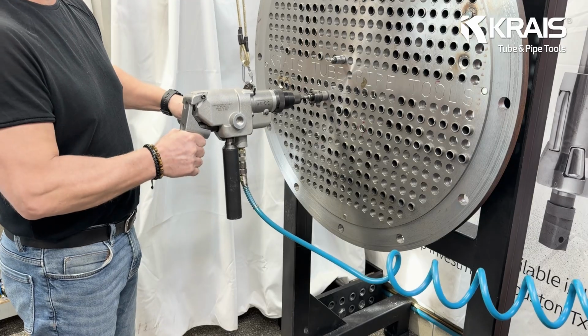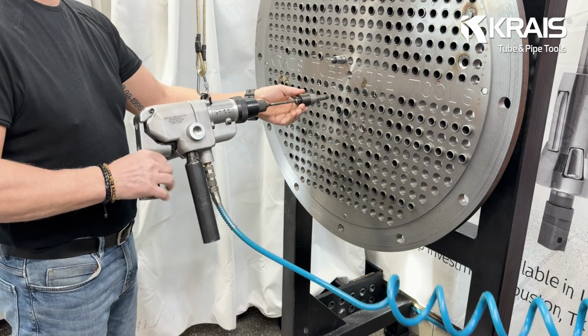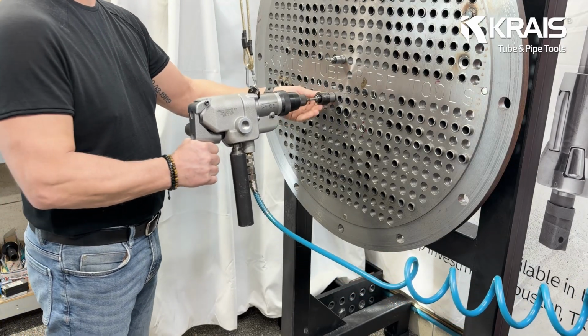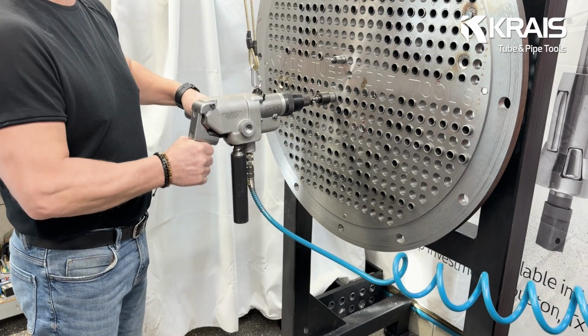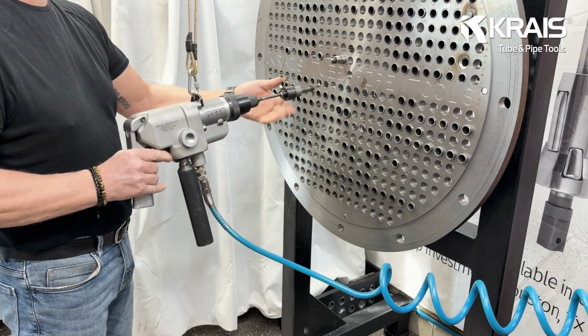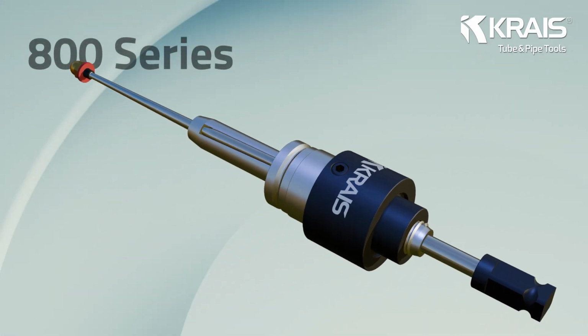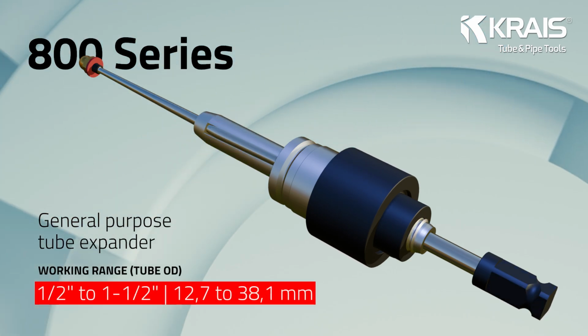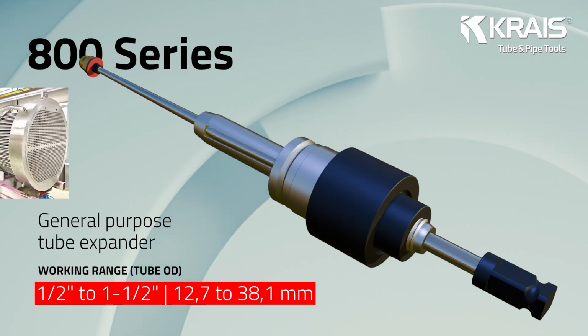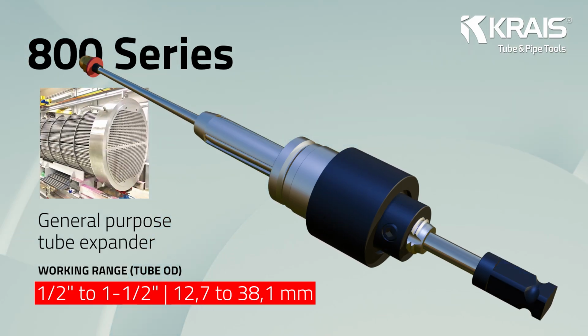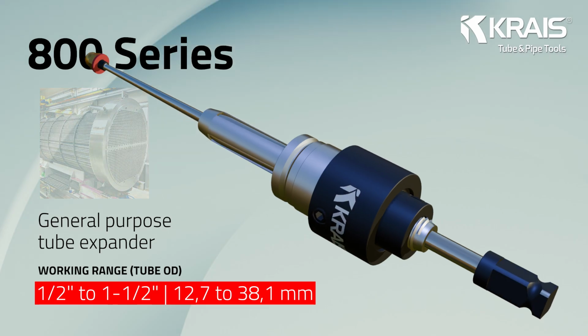In this segment, you will most often see tube ODs from 1/2 inch up to 1.5 inches, a wide range of tube sheet thicknesses, and significantly more variation in materials. KRAIS 800 series expanders are the baseline general-purpose family for the most common tube sizes in exchangers and condensers. Choose it for typical diameters and standard tube sheet thicknesses when you need efficient, uniform rolling without special joint requirements.